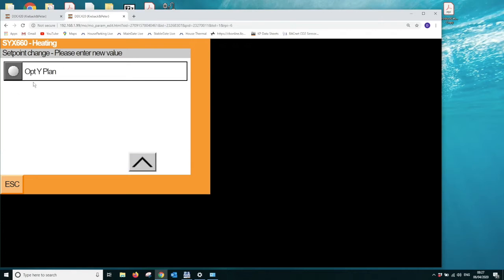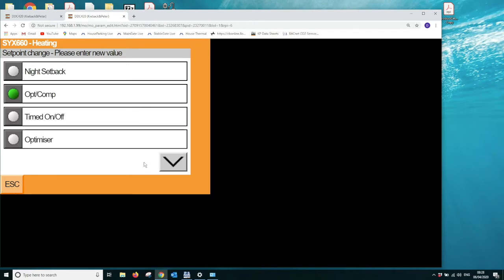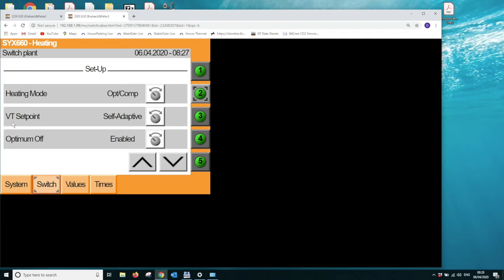The next option at the bottom of the list is the optimized Y plan. This is for large domestic applications where it will conform to the Y plan, which is the typical domestic arrangement, but this is an enhanced feature of the Y plan in that we optimize the heating circuit. Okay, so we're going to leave this set at optimizer compensator, and we're going to look at the next option, VT set point. VT set point says self-adaptive.